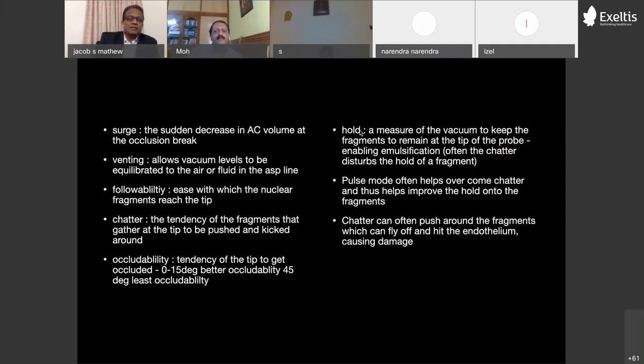So this is something that is taken care of with the computer chips I mentioned, which are there in the handpiece as well as in the pedal and the console. They sense where the occlusion break occurs, and immediately there is something called venting that takes place, where it equilibrates the vacuum levels with either air or fluid in the aspiration line, causing it to balance out at the quickest and causing as little surge as possible.